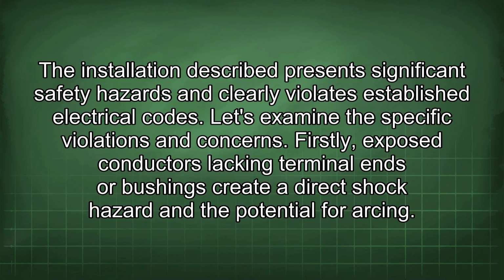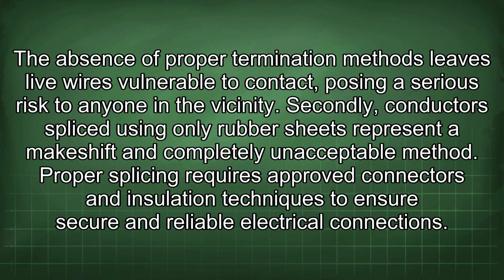The installation described presents significant safety hazards and clearly violates established electrical codes. Let's examine the specific violations and concerns. Firstly, exposed conductors lacking terminal ends or bushings create a direct shock hazard and the potential for arcing. The absence of proper termination methods leaves live wires vulnerable to contact, posing a serious risk to anyone in the vicinity. Secondly, conductors spliced using only rubber sheets represent a makeshift and completely unacceptable method.